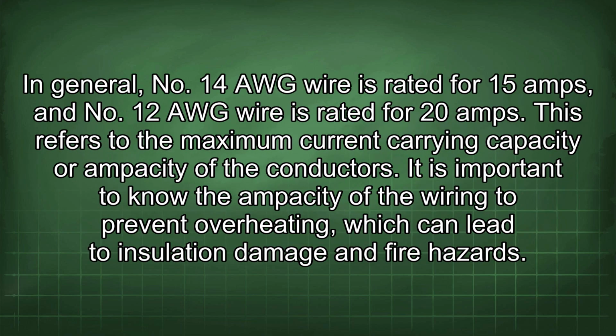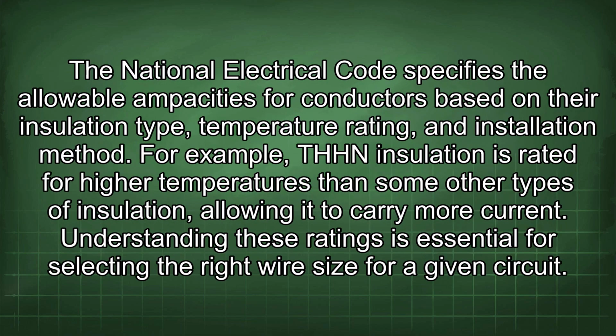In general, No. 14 AWG wire is rated for 15 amps and No. 12 AWG wire is rated for 20 amps. This refers to the maximum current carrying capacity or ampacity of the conductors. It is important to know the ampacity of the wiring to prevent overheating, which can lead to insulation damage and fire hazards. The National Electrical Code specifies the allowable ampacities for conductors based on their insulation type, temperature rating, and installation method. For example, THHN insulation is rated for higher temperatures than some other types of insulation, allowing it to carry more current. Understanding these ratings is essential for selecting the right wire size for a given circuit.